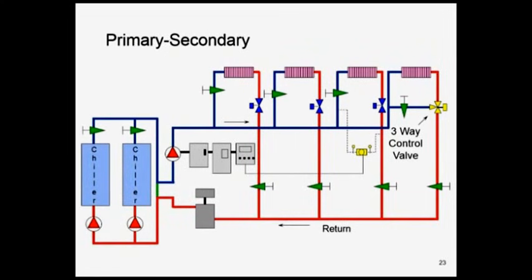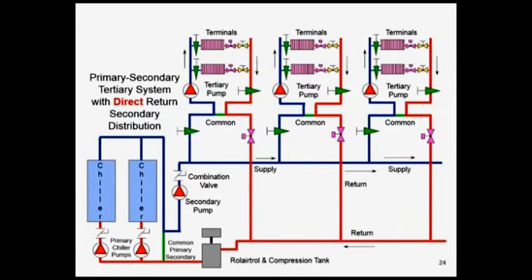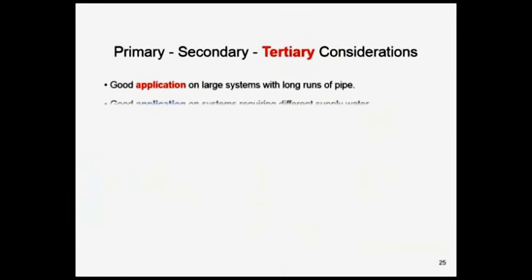Here's a traditional primary, secondary piping setup. Constant flow through the chillers, the little green pipe is the decoupler, and you see the secondary pump with 2-way valves. Traditional, primary, secondary. Fine, good system. Here's primary, secondary, tertiary. And you see the little green common pipe at the chiller loop, the green in each building. I got 3 sets of pumps, primary, secondary, tertiary, to take advantage of diversity. All I'm asking you to do is recognize the system. I'm not saying any of these systems any better than another one.